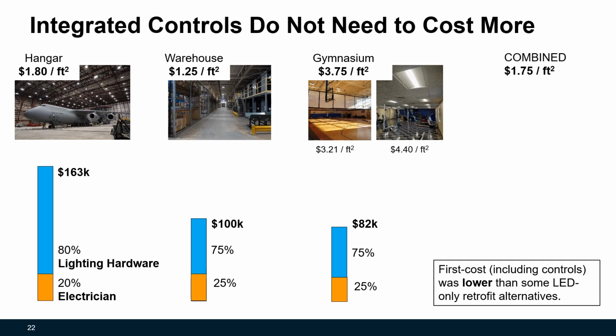Most people expect that wireless lighting controls are always too expensive. We found that integrated controls can actually reduce the initial costs compared to hardwired controls. Over the 3 test facilities, the total cost of the retrofit, including the installation and configuration, was less than $2 per square foot, and most of that cost came down to hardware. The installation effort was not that different from an ordinary LED retrofit.